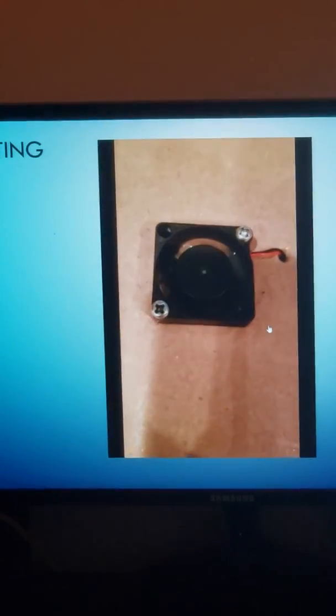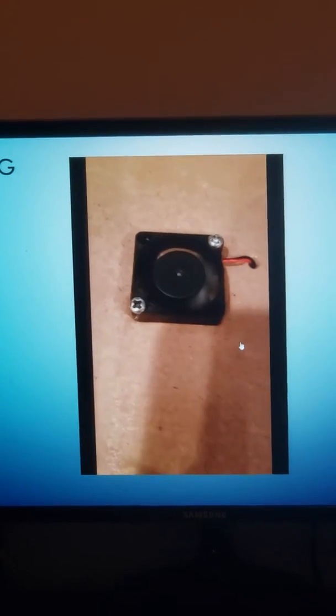Alright, this is the test mock-up. We are at the first step where it's 88 degrees. It's still green, we're not in alarm state, but we have energized the fan. See, it's energized right there, I'm blowing.